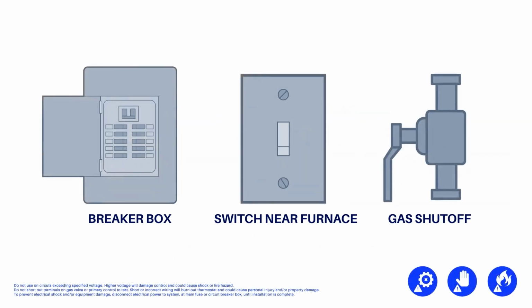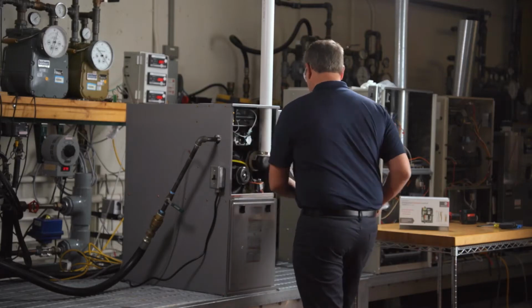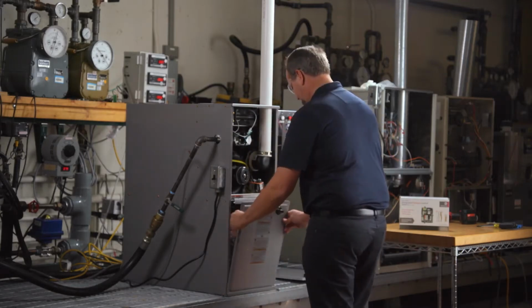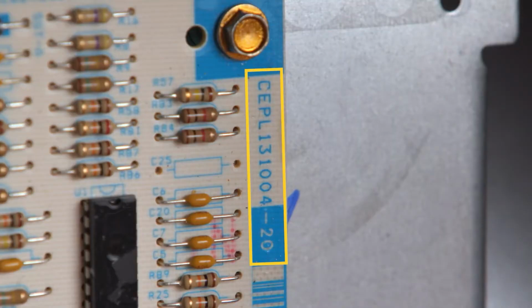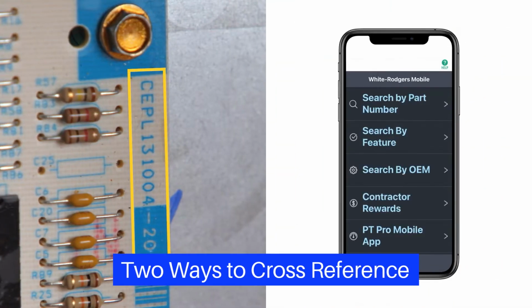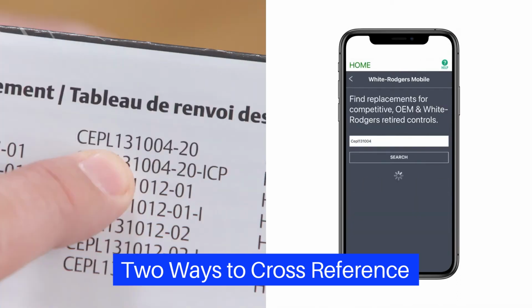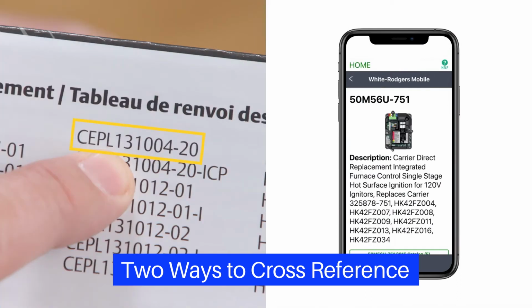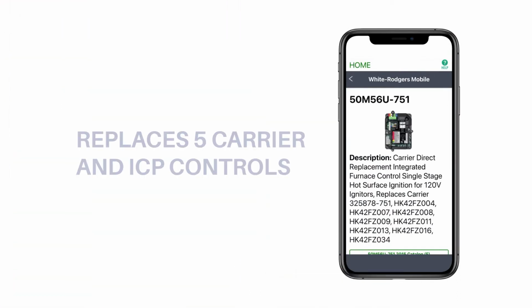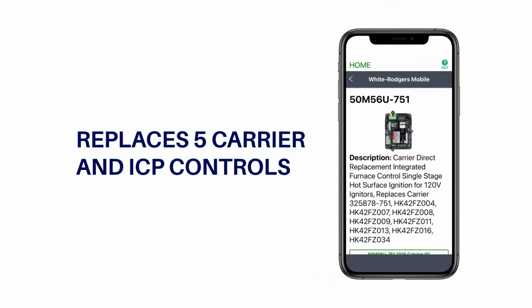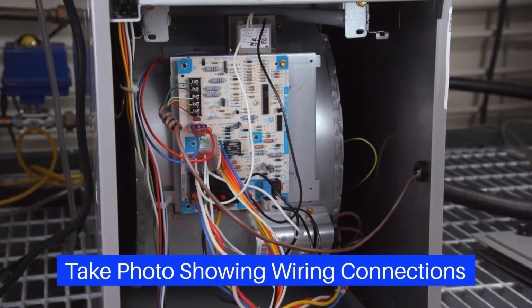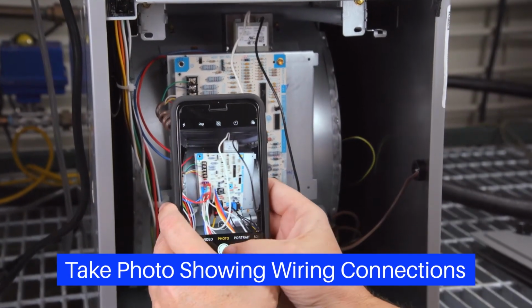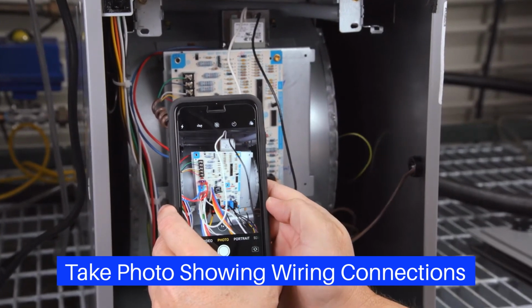First, ensure power and gas are disconnected prior to servicing the furnace. Remove the unit access panels. Check the part number on the existing control and verify it can be replaced with the 50M56U-751 using the cross-reference on the side of the carton or the White-Rodgers mobile app. This control replaces 5 Carrier ICP controls. Take a picture of the existing control for reference before disconnecting wires.